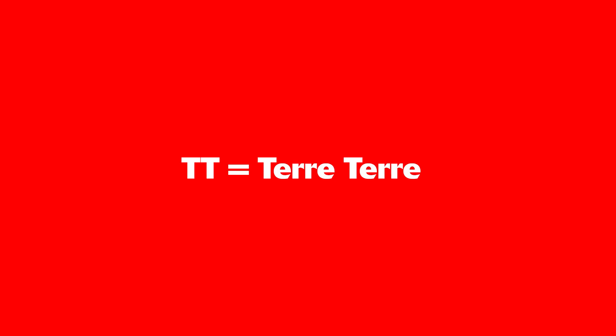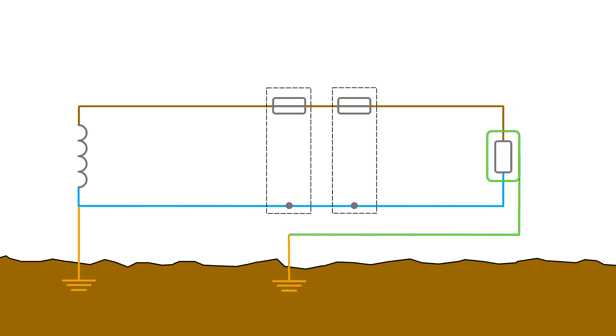The designation TT just indicates that the supply provider and the installation have their own connection to the literal earth connecting them together. Again we find ourselves in a position where in the event that a fault occurs and the line conductor comes into contact with say the metal casing of a load the path the current takes through the literal earth has a really high value and it may not be enough to cause an MCB to trip leaving us with a live metal part that someone could touch and get a shock from.